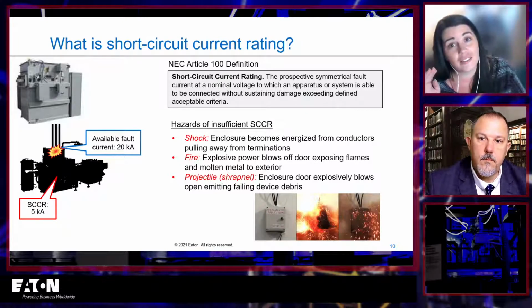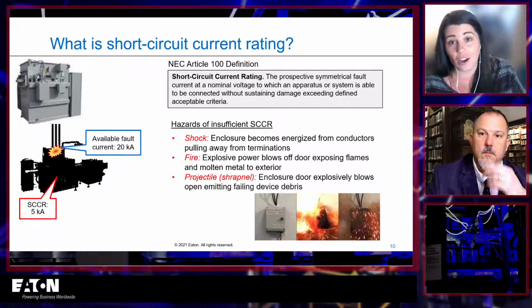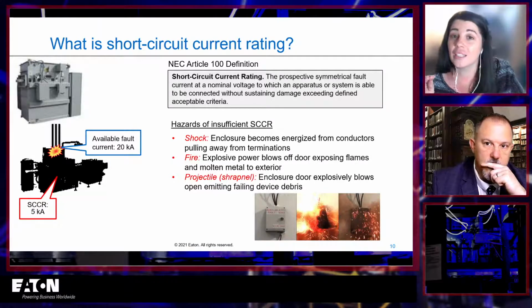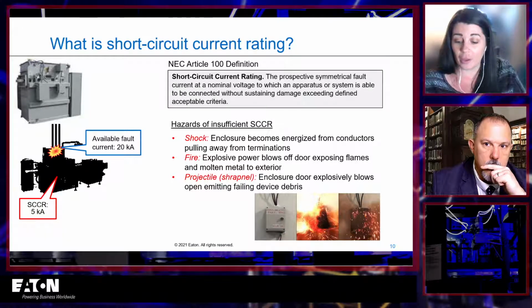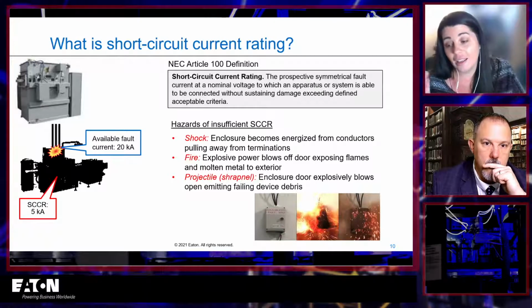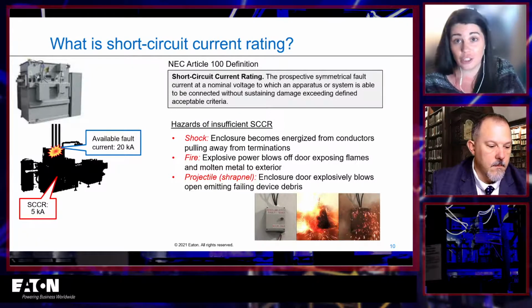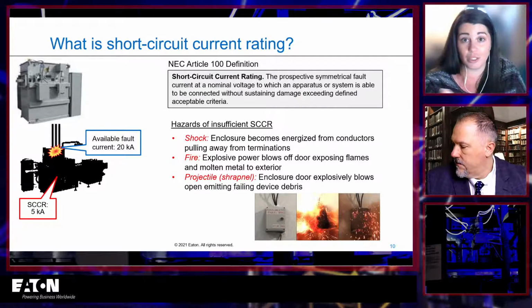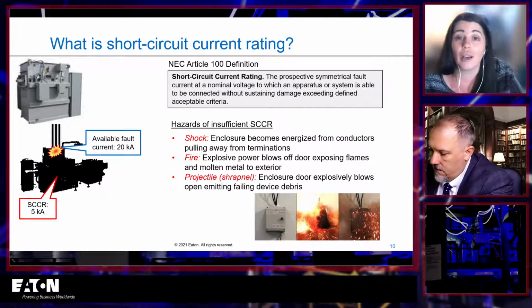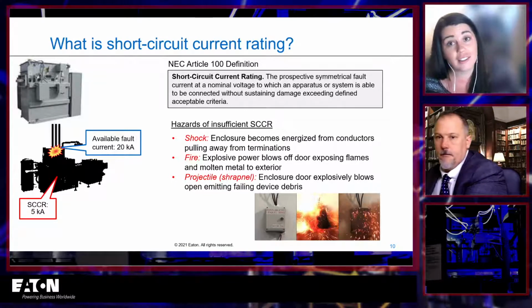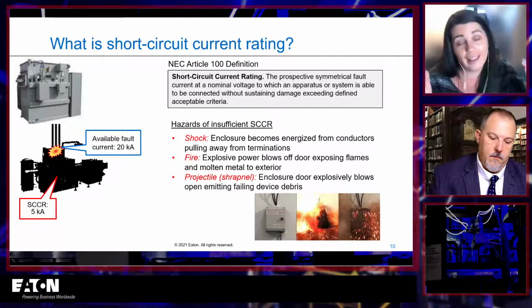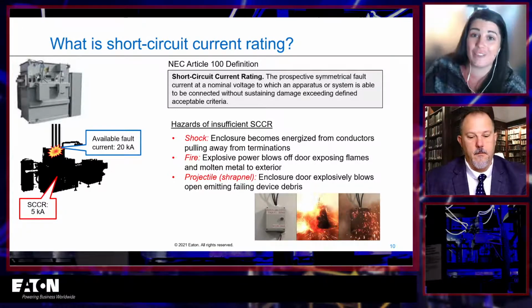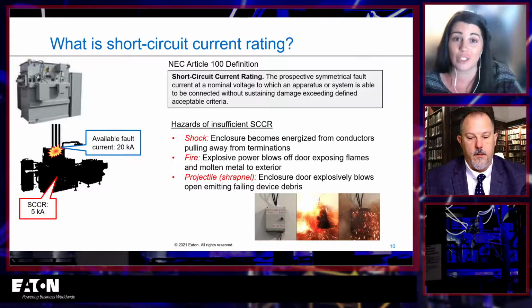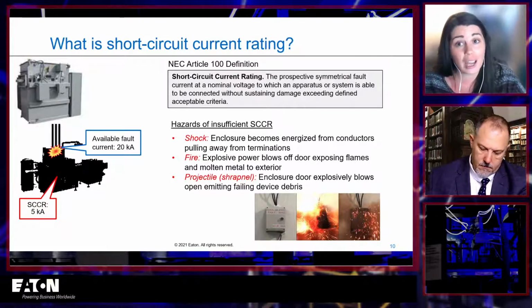I always like to stress at this point that SCCR, the short circuit current rating of equipment, does not mean that the piece of equipment will be able to be used again immediately, right? It does not mean there's no damage to it at all. It just means no damage exceeding a certain amount. So if I can create a small fire inside of it, and as long as the door doesn't blow up and I'm okay, then obviously I'm not going to be able to use that piece of equipment again immediately. There's going to have to be some changes made. So it's a different type of protection.